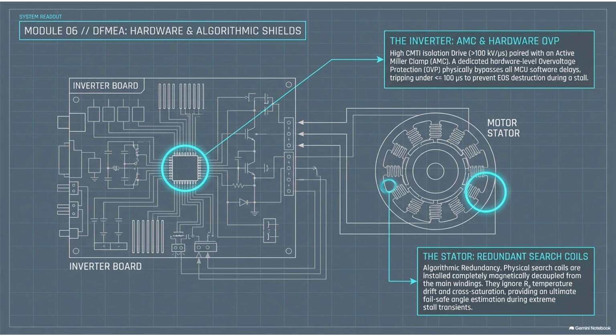You give the system a compass that simply cannot be corrupted. The specification mandates the inclusion of search coils. This is a form of algorithmic redundancy built right into the physical copper and steel of the motor. Engineers literally designed the blueprints to include tiny redundant wire coils hidden deep inside the stator slots. Hidden coils, like secret backup sensors woven into the main motor. Exactly. And the brilliance of these search coils is that they have absolutely zero physical or electrical connection to the main high-voltage power cables. They do not carry the massive driving current.